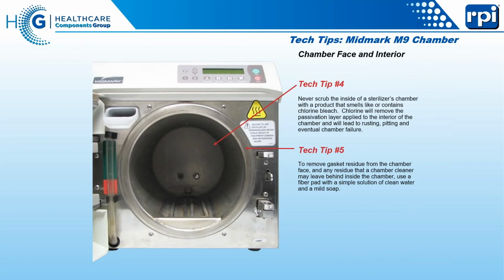Now, the other part of the story about door gaskets falling out is all door gaskets are made out of silicone. They are replaced yearly for a reason, because over that year they tend to shrink. There's nothing wrong with a gasket that has shrunken as long as it continues to seal. But if you do find that you've cleaned this surface and the gasket just seems to still be falling out, you let us know. We certainly will be interested in seeing that. That's kind of the reason why Midmark put that wire in their door gasket. They decided that they would solve the problem of shrinking silicone by giving it something to shrink against. Unfortunately, it didn't work that way. Silicone continues to shrink no matter what Midmark thinks.